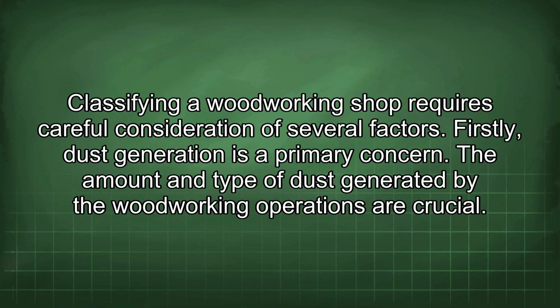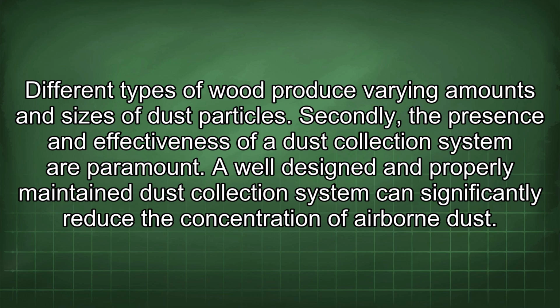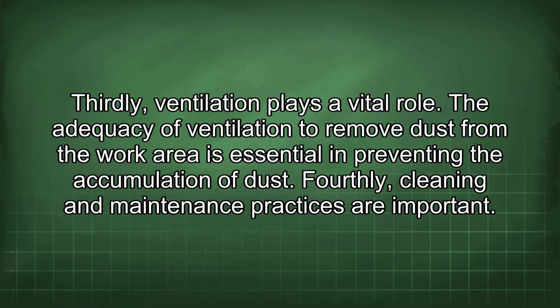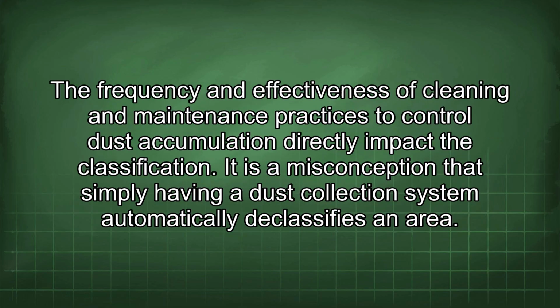Classifying a woodworking shop requires careful consideration of several factors. Firstly, dust generation is a primary concern. The amount and type of dust generated by the woodworking operations are crucial. Different types of wood produce varying amounts and sizes of dust particles. Secondly, the presence and effectiveness of a dust collection system are paramount. A well-designed and properly maintained dust collection system can significantly reduce the concentration of airborne dust. Thirdly, ventilation plays a vital role. The adequacy of ventilation to remove dust from the work area is essential in preventing the accumulation of dust. Fourthly, cleaning and maintenance practices are important. The frequency and effectiveness of cleaning and maintenance practices to control dust accumulation directly impact the classification.